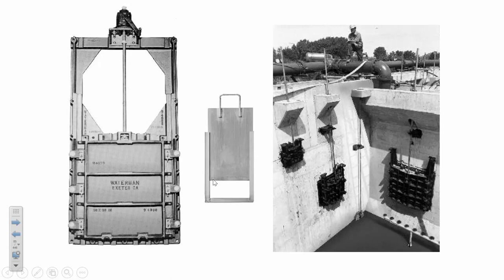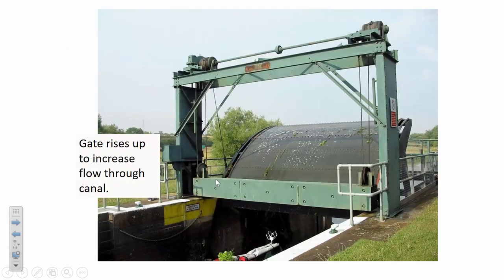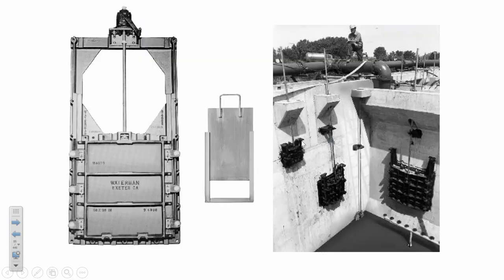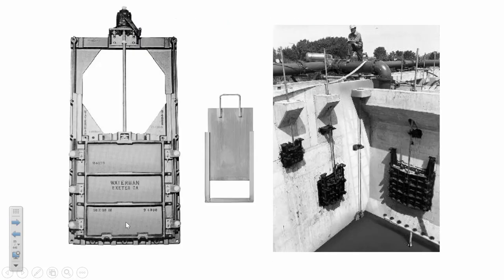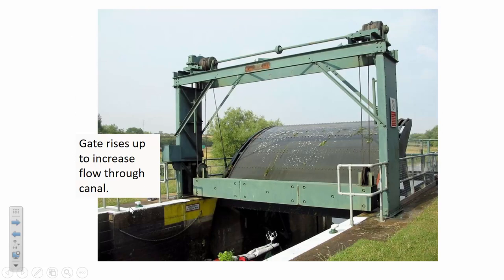Gates are used both in irrigation applications and in water and wastewater treatment to regulate flow in and out of stilling basins, aeration basins, flow equalization basins, and disinfection tanks. A radial gate has an advantage: as water level rises, it doesn't become harder to open, because all forces push toward the central pivot point, creating no moment that pins the gate closed — unlike a gate in a frame where deeper water means greater friction.